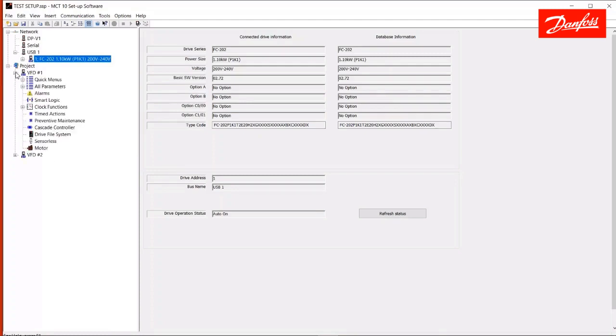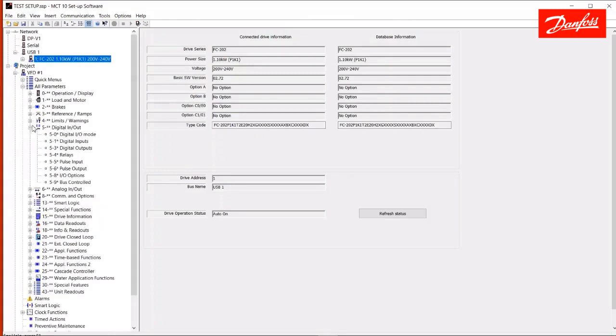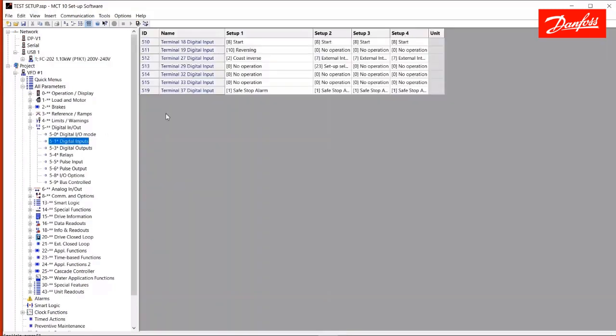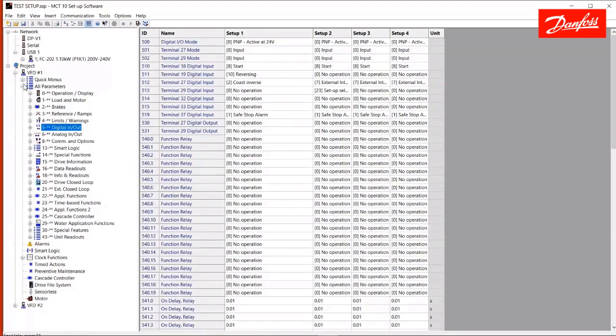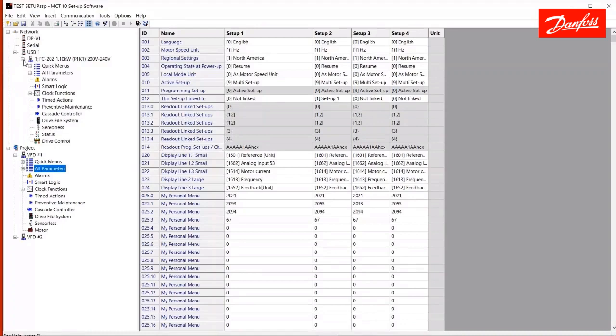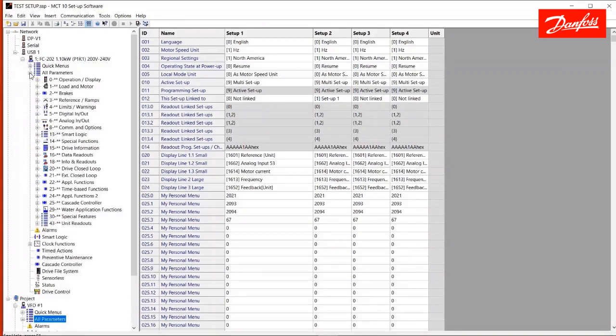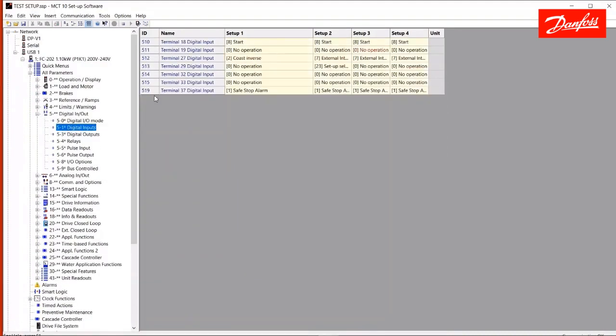So, before I do that, I want to make one change, so we can see something happen here. Actually, I've already made that change. Just to show you again, I've changed this digital input from the default value of no operation to reversing. That value is left default on the live drive here. It is no operation.